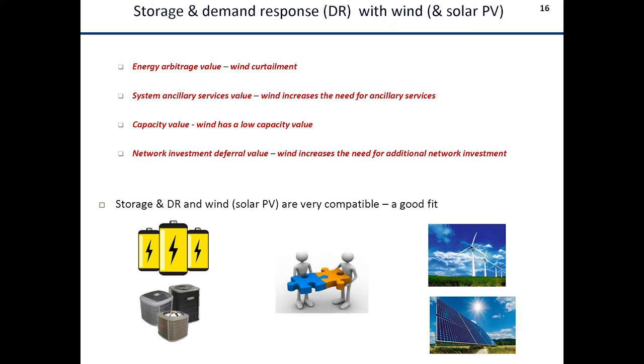Capacity value is a quantification of the amount of extra customers you can serve while maintaining the same level of reliability with a generator. So if I have a 100 megawatt generator with a capacity value of 80%, it means you can serve 80 megawatts more load continuously during the year, maintaining the same reliability. It can never be greater than 100%, because of maintenance and breakdowns. So storage can also produce capacity value.